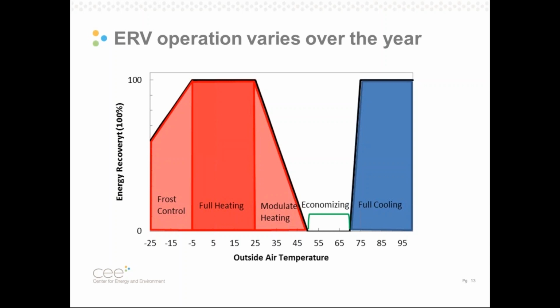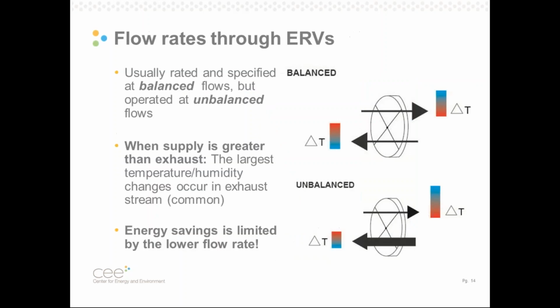And so one way to do that, there are many methods for frost control, is to, again, start limiting energy recovery. If we reduce its effectiveness, we can increase the exhaust temperatures and stay out of that zone. So you can see here that energy recovery actually does a lot. There are about 5 discrete things an energy recovery system has to do throughout the year. So we can imagine there's a lot of sequencing that has to go on to make automation systems do this properly, and then it also has to interact well with heating and cooling systems. So it's fair to say that energy recovery systems, or properly implementing them, is pretty complicated.